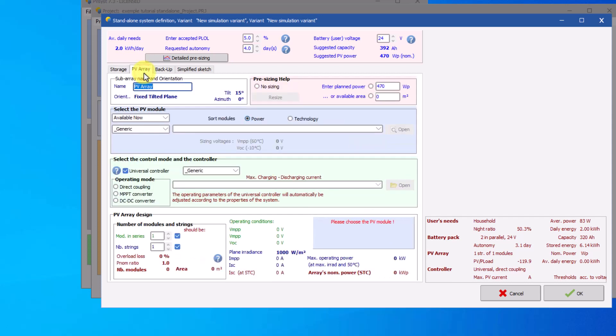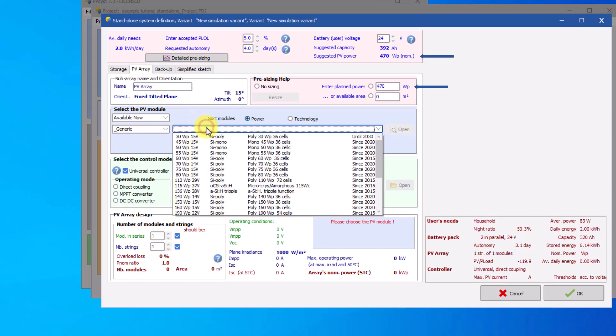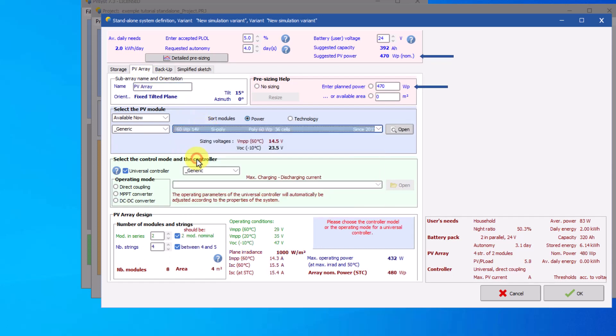The pre-sizing tool recommends a peak power of the PV array. Select PV module from the database. For each selected module, the software shows the voltage sizing. You can read the voltage at the MPP at 60 degrees, and then the open circuit voltage at minus 10 degrees for this module.